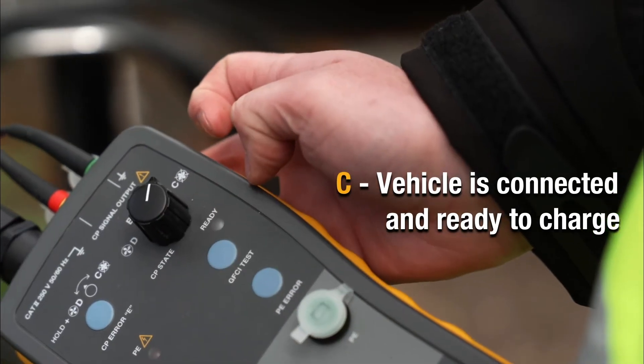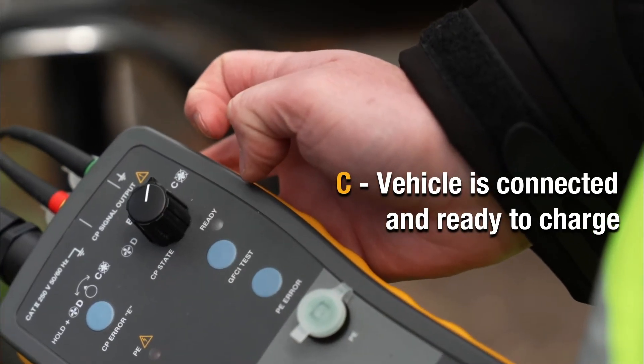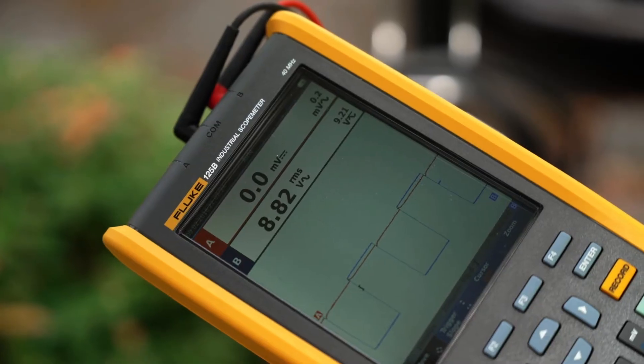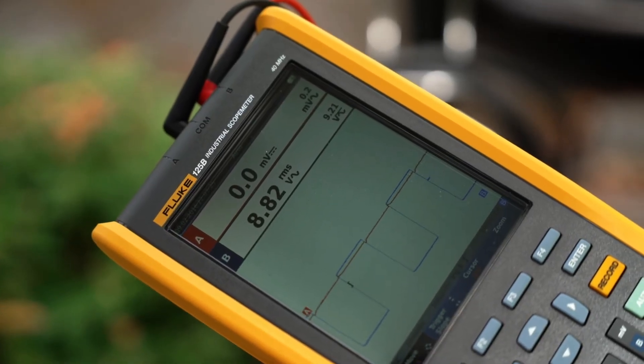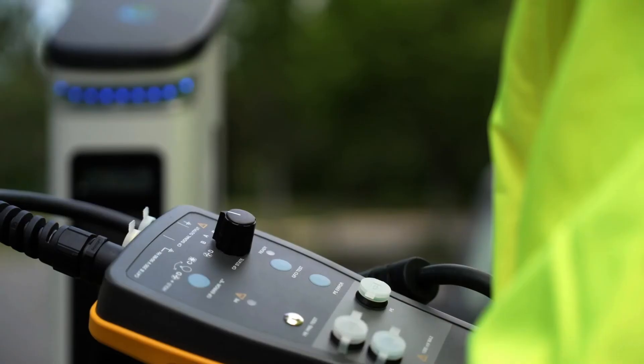Then switch the button to the C position to test the state where the vehicle is connected and ready to charge. Your scope meter should indicate negative 12 volts to positive 6 volts at 1 kHz frequency.